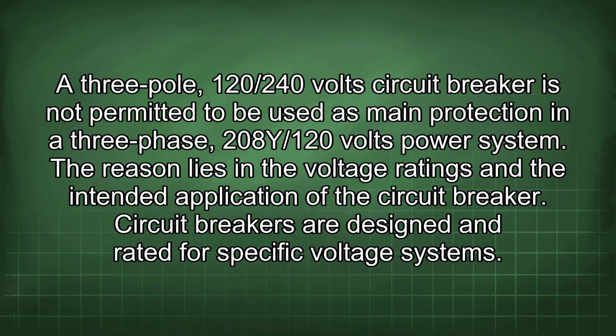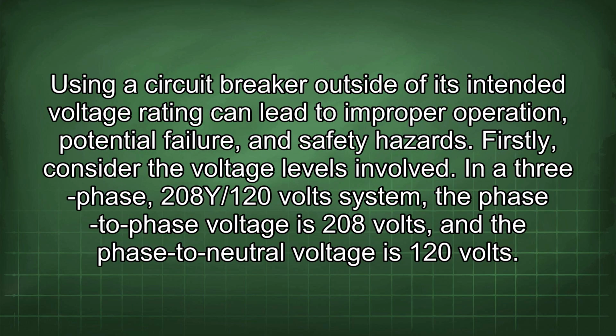3-pole 120/240 volts circuit breaker is not permitted to be used as main protection in a 3-phase 208Y/120 volts power system. The reason lies in the voltage ratings and the intended application of the circuit breaker. Circuit breakers are designed and rated for specific voltage systems. Using a circuit breaker outside of its intended voltage rating can lead to improper operation, potential failure, and safety hazards.